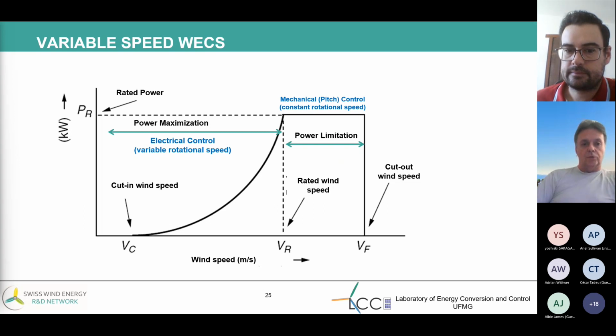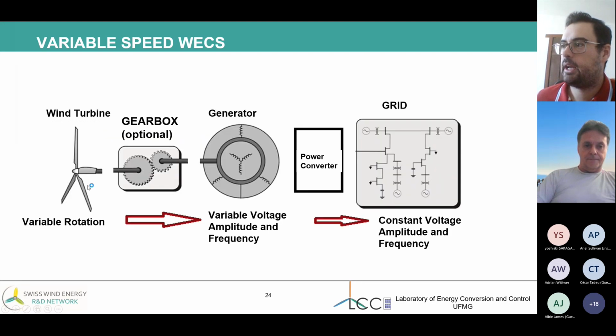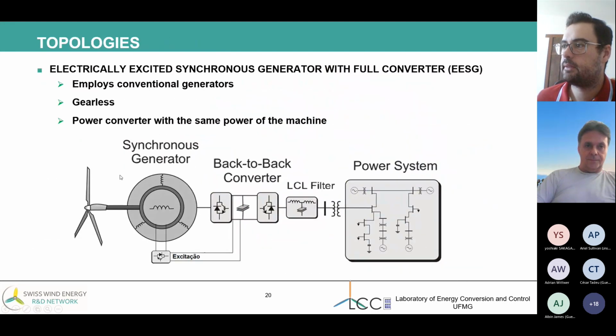Then below the rated speed, you talk about electrical control. Does this electrical control also generate some mechanical actions on the turbine? Yes, the rotational speed. The control is electric, in the electric generator, and the action is to change the rotational speed.